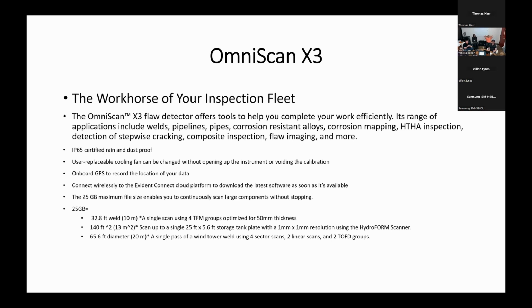So it is IP65 certified, rain and dust proof. It has a replaceable cooling fan on the backside, so you can replace that without voiding the calibration of the instrument. It has onboard GPS to record the location of your data, and also used in the event that your machine gets stolen or lost. It is restricted in some areas, or not available in some areas. You can also connect wirelessly to the Evident Connect cloud platform to download the latest software as soon as it's available. So you set a Wi-Fi connection, you can upload the latest software through that.